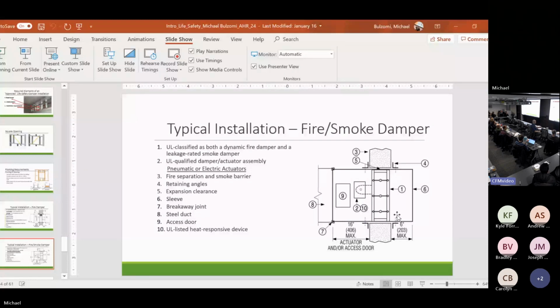If you buy them from me as a manufacturer, I make 2 size angles. One with a 1.5 inch leg, one with a 2 inch leg. I had a contractor make his openings as big as they could be. He needed a 5 inch leg on his angle. Well, they ordered angles from me thinking that they were going to cover the opening. I said, no, my angle's 1.5 inch by 1.5 inch. You have to fabricate that yourself. So again, that expansion clearance is important to the function of the damper. The one thing that can never happen is putting anything in there. So if an inspector says, hey, I know there's a gap around this damper where smoke can penetrate or flame can penetrate, put fire wool, put rock wool, put intumescent. No, do not ever put anything in the gap. It's in my installation instructions. It voids the UL listing of the damper.